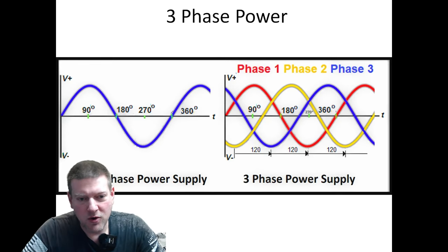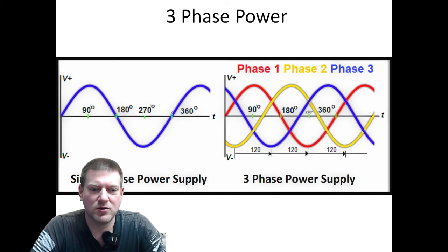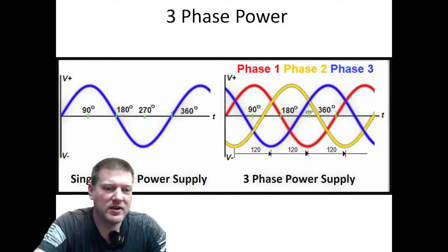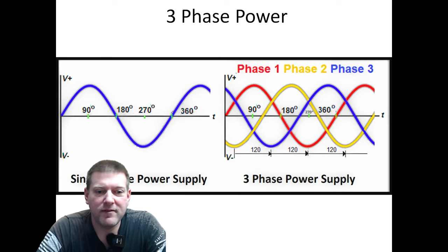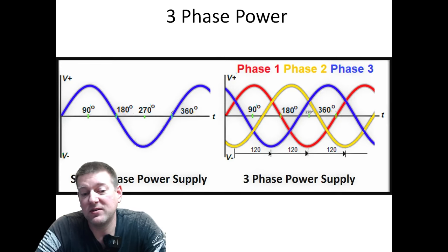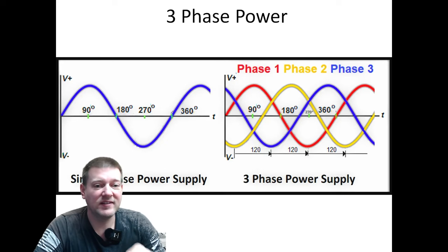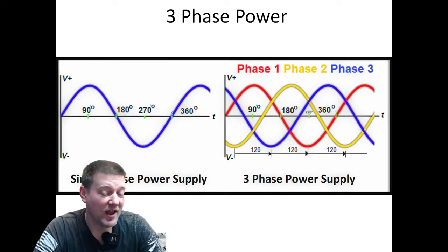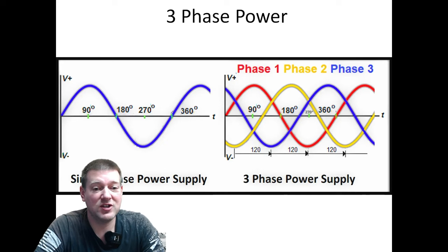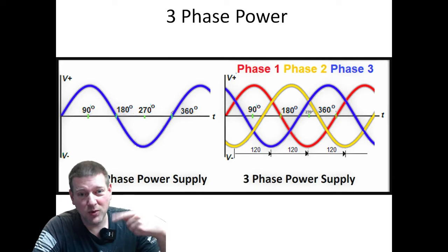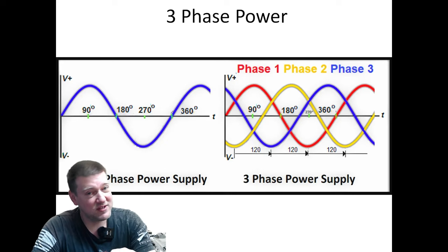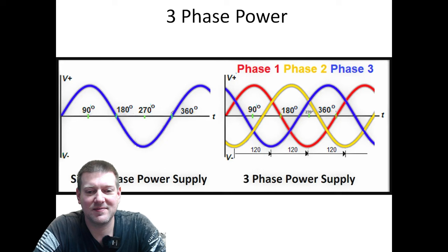If you take a normal two-pole motor, that's a north and south magnet, you're going to have a normal looking sine wave, as shown here. Your sine wave is going to have a frequency of 60 hertz, that's 60 times per second. So if you want a sine wave to be 60 hertz on a generator, that generator has to rotate at 3600 RPMs because it's 60 times a second times 60 seconds.